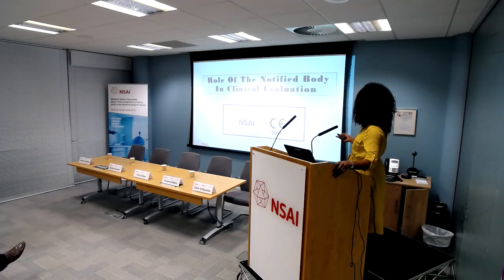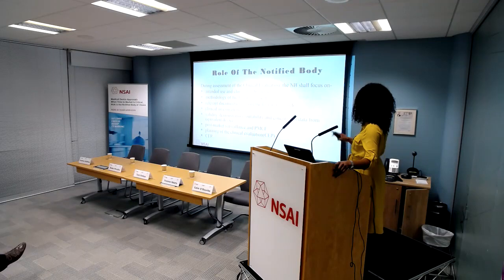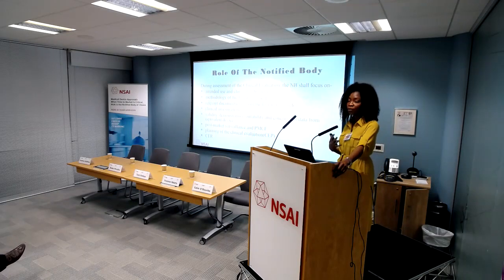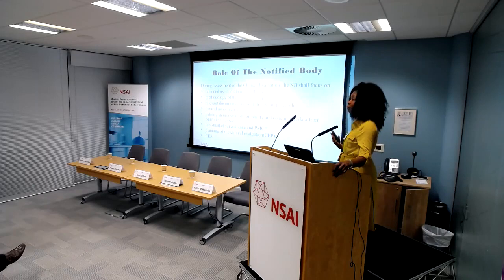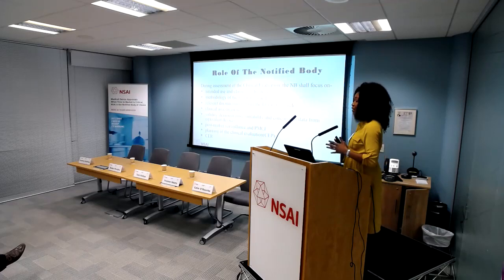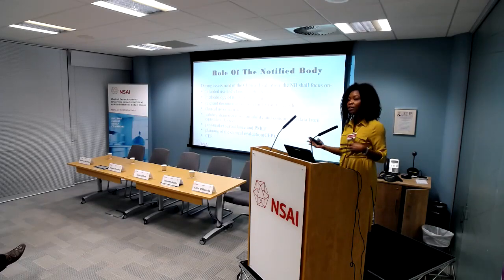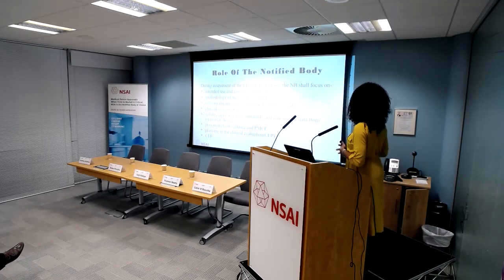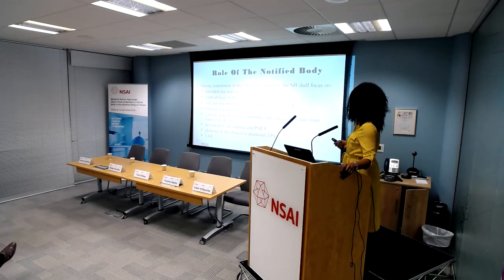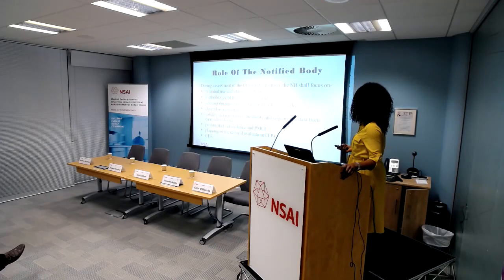So that's just talking about the role of the notified body in a clinical evaluation. In summary, from a clinical point of view, what I would be looking at when I'm looking at your device and the clinical data is what you have stated your intended use to be. I'd be looking at traceability of your intended use across all the other documents. So I have to see that your intended use in your clinical evaluation report, your risk management document and your IFU are actually aligning with each other. I'd be looking at your literature search. I'd look at your clinical investigation data, your post-market surveillance data, PMCF, and how you plan your clinical evaluation.